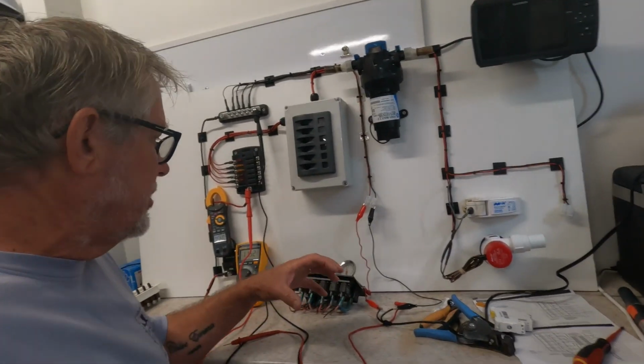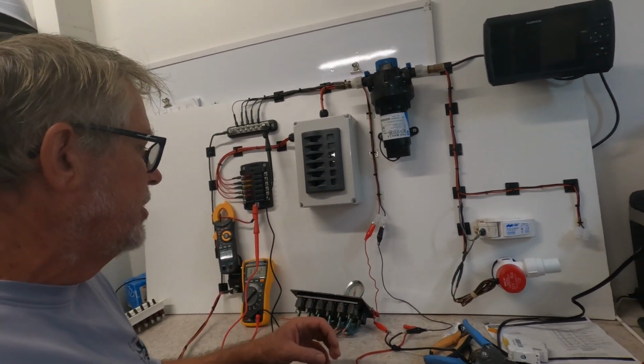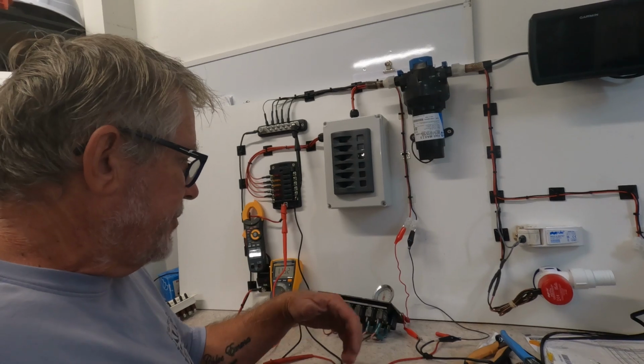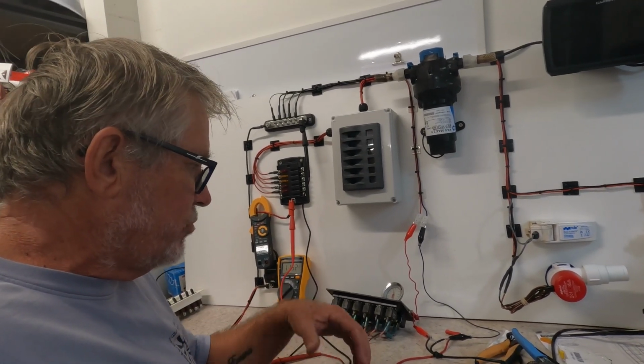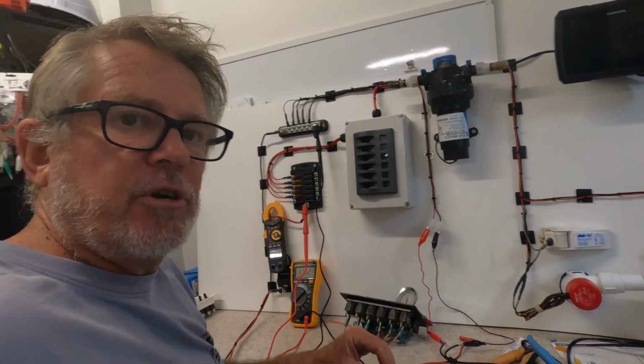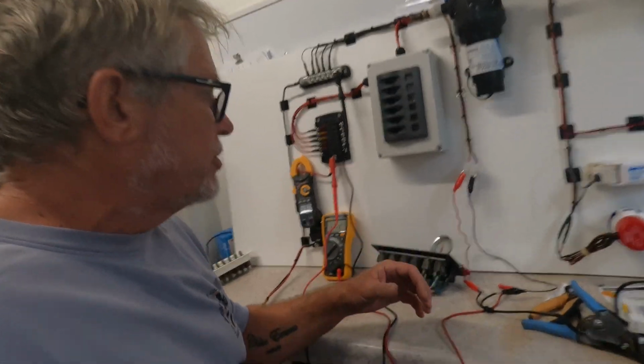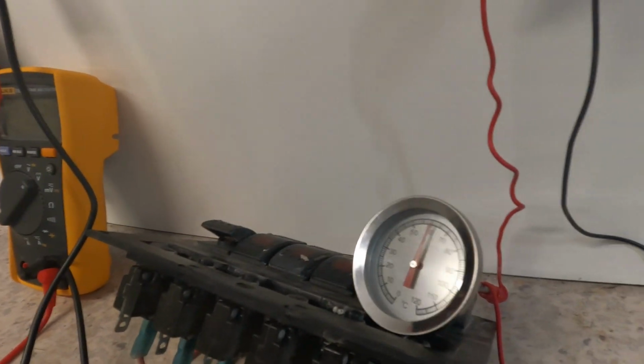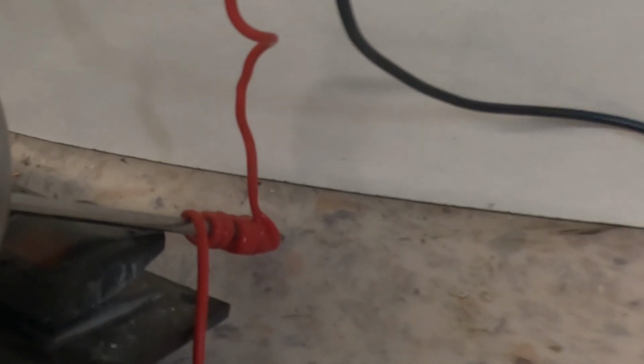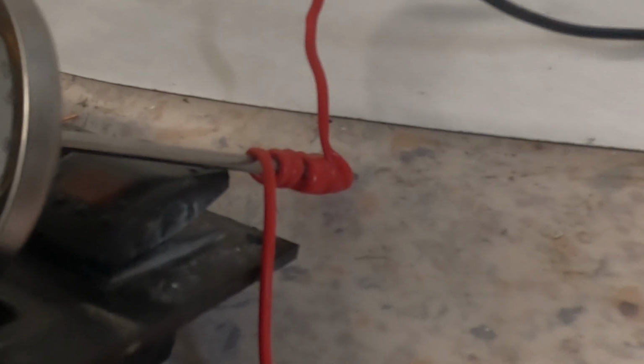So that proves a point, guys. The point I was trying to prove is pretty simple: you must set up the right wire or cable for the load you've got at the other end of it. If your wire's too small, you're going to have a problem like this. There we go, starting to melt.